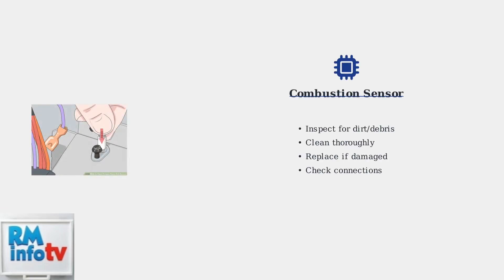The combustion sensor is another component that can trigger error code 13. A dirty combustion sensor prevents proper flame detection, so it needs regular cleaning or replacement when necessary.